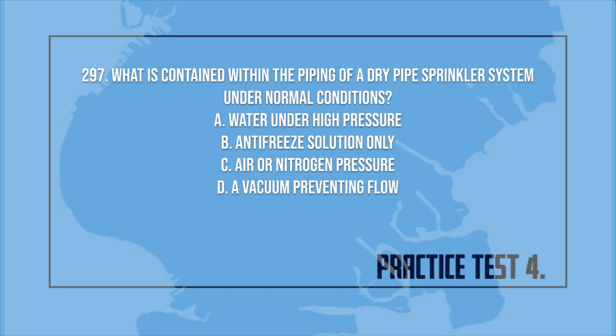297. What is contained within the piping of a dry pipe sprinkler system under normal conditions? A. Water under high pressure. B. Antifreeze solution only. C. Air or nitrogen pressure. D. A vacuum preventing flow.